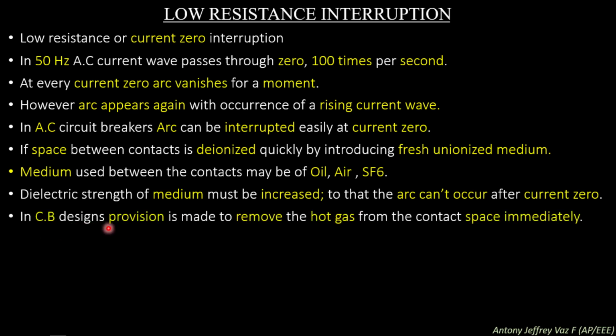In circuit breaker designs, provision is made to remove the hot gas from the contact space immediately. In all circuit breakers such as air, oil or SF6 circuit breakers, the interrupter or the circuit breaker design should be provided in such a way that the space where the arc occurs should be deionized immediately after the current zero position has occurred.